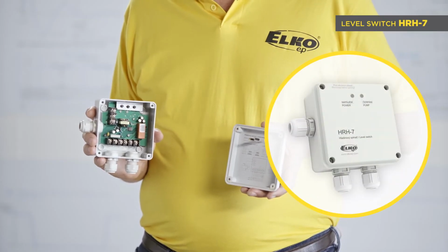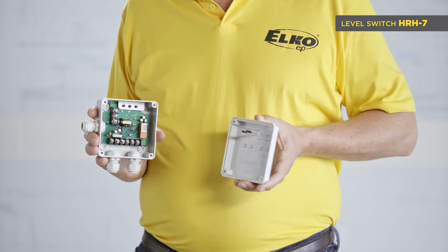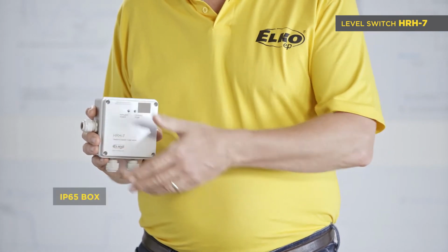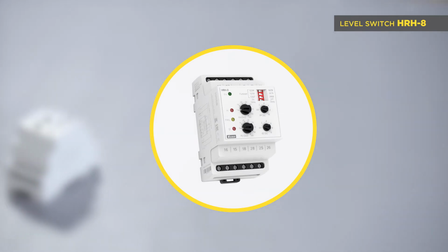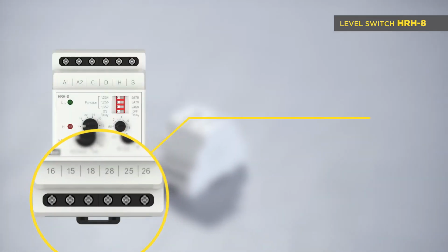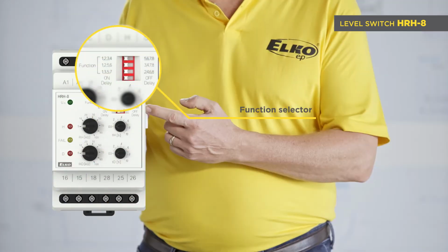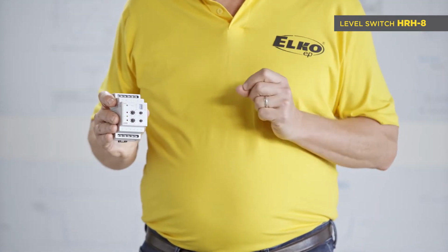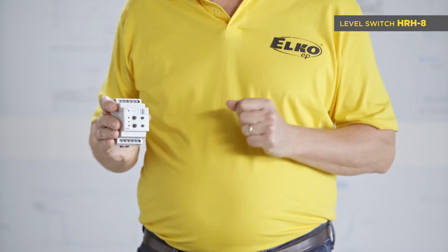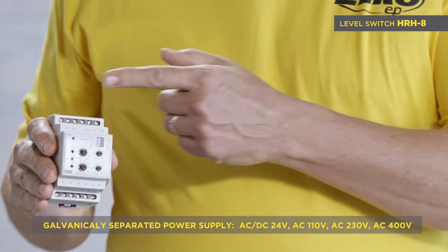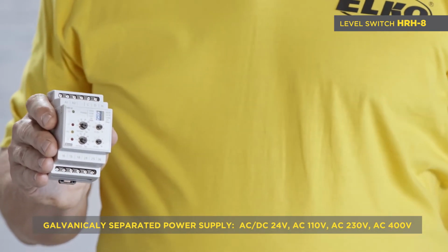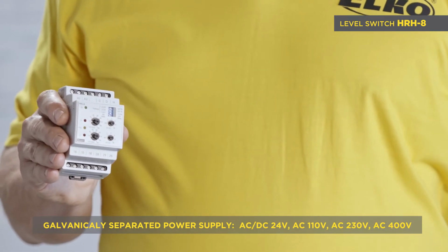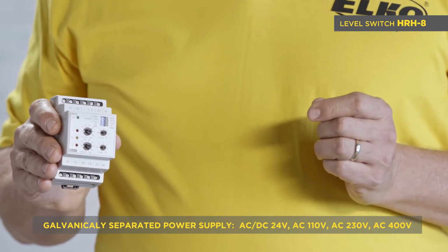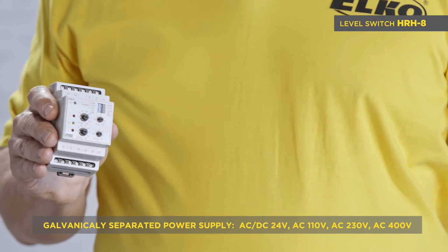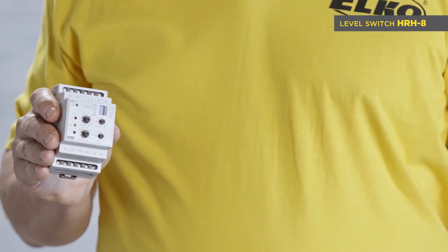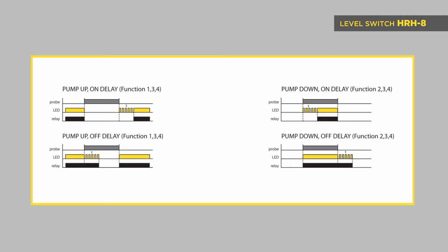HRH7 has identical functions as the previous HRH5, but is designed in an enclosure with IP65 protection. HRH8 has 8 functions thanks to 2 independent output relays and function selector on the front panel. The key advantage is the possibility to have 2 separate one-level monitoring in 2 tanks. The galvanically separated power supply from monitoring inputs comes in 4 options: AC/DC 24 volt and AC 110, 230, and 400 volts. Other parameters are identical with the HRH5. This features the following functions.